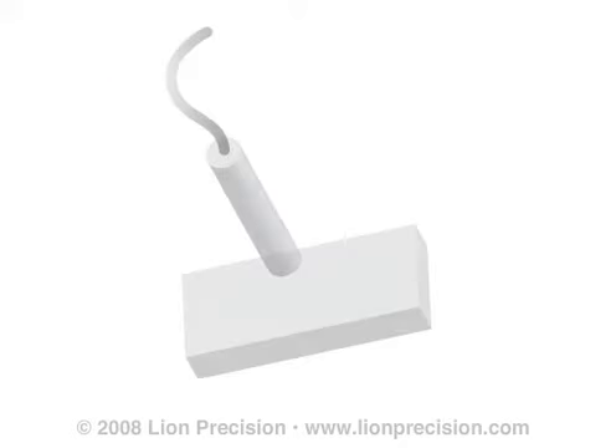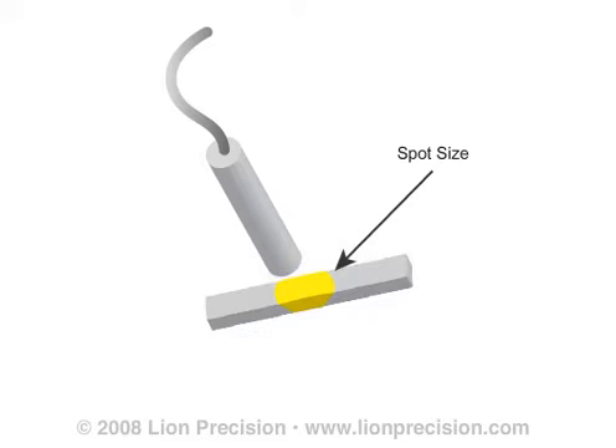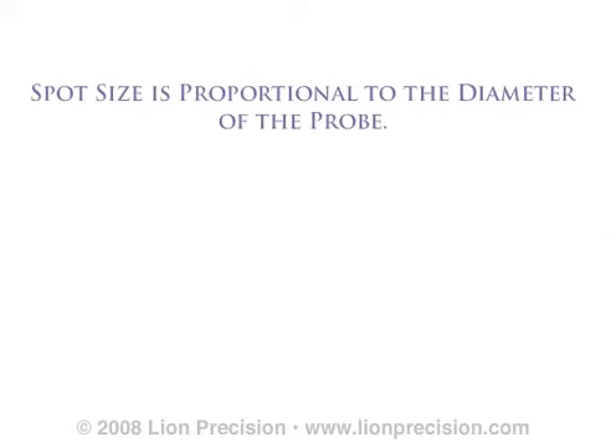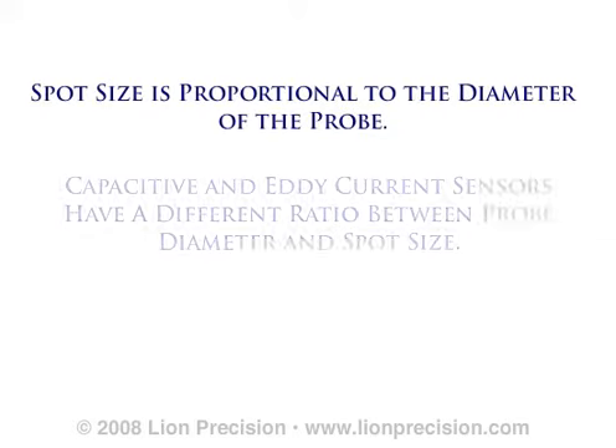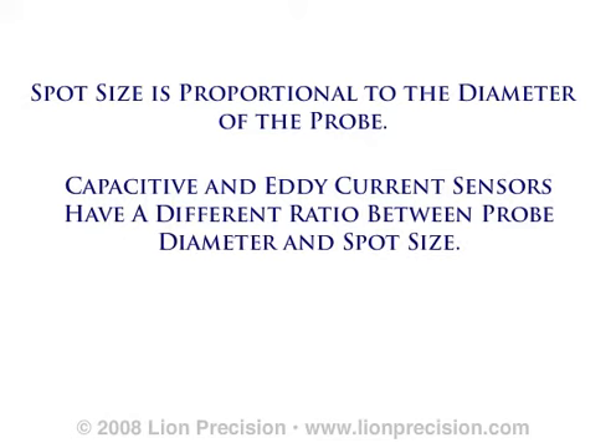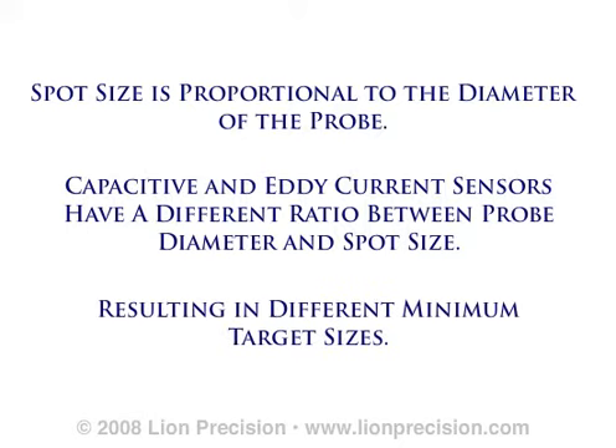The sensing field of a non-contact sensor's probe engages the target over a certain area. The size of this area is called the spot size. The target must be larger than the spot size, or special calibration will be required. Spot size is always proportional to the diameter of the probe. The ratio between probe diameter and spot size is significantly different for capacitive and eddy current sensors. These different spot sizes result in different minimum target sizes.